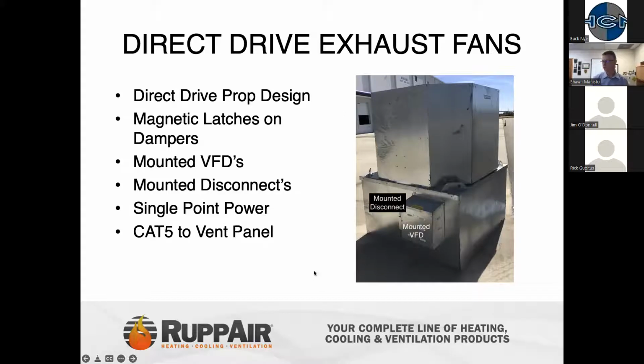This actually is one of our fans we build. It's actually a Prop 5 direct drive, but we have pre-mounted VFDs, pre-mounted disconnects. It's basically a single point power source. And actually for these products here, all they run is 3-phase power to the disconnect, and then they run a Cat 5 up to the unit for interfacing with this fan.